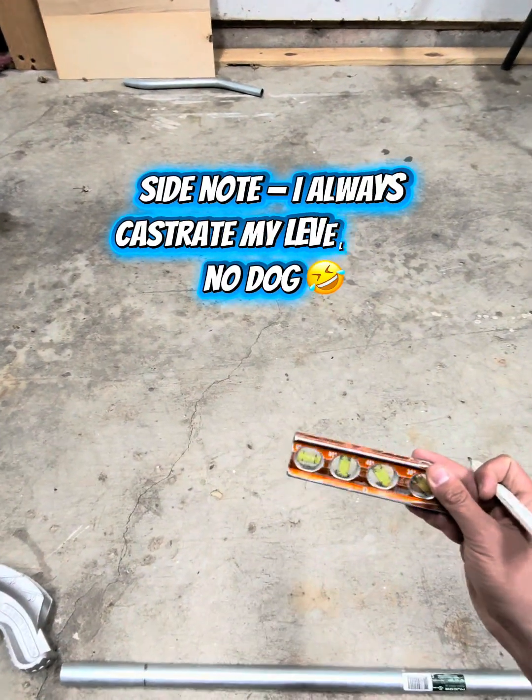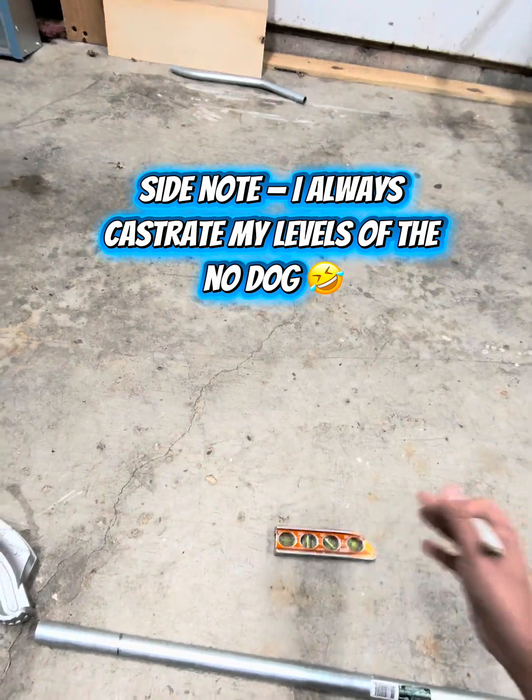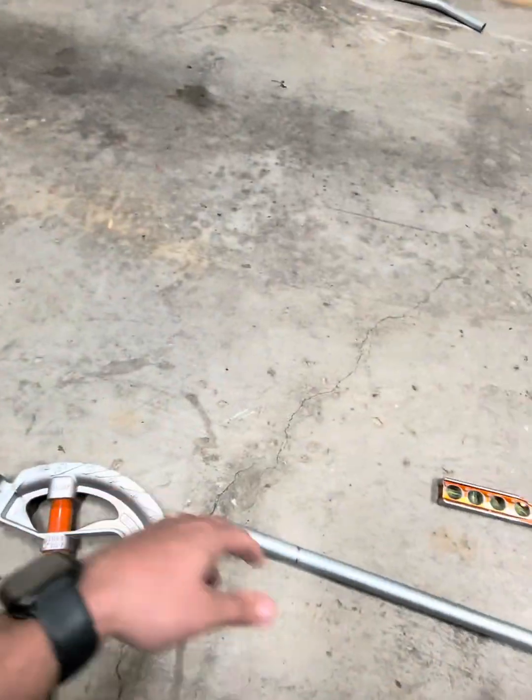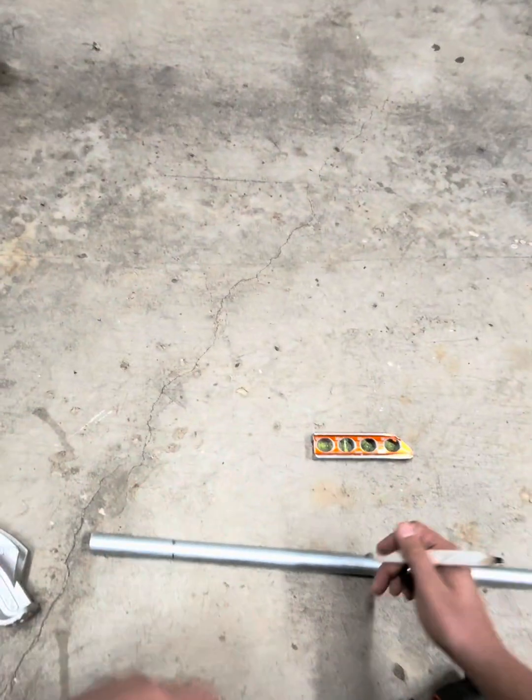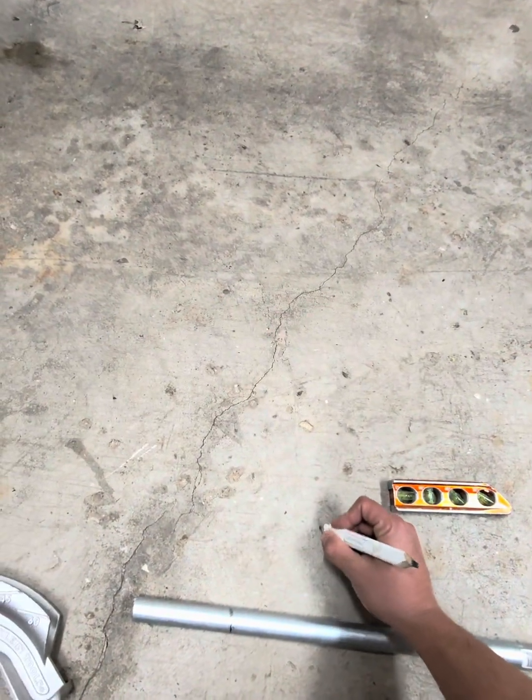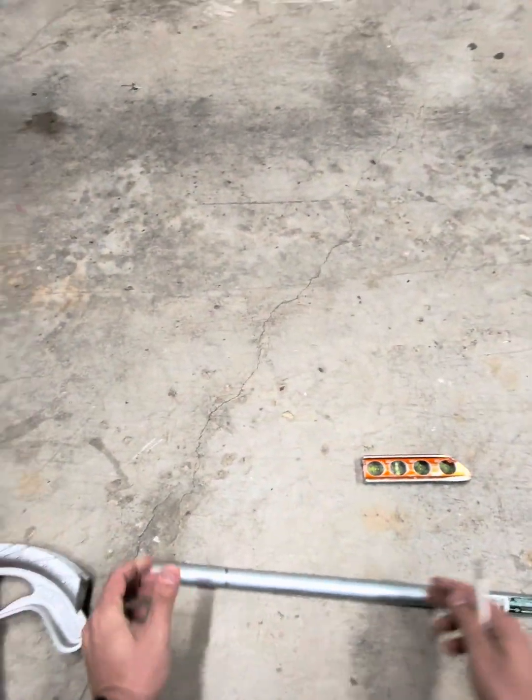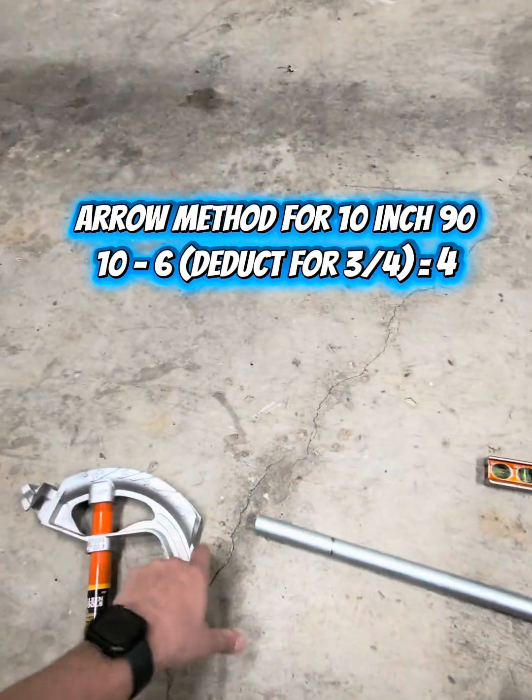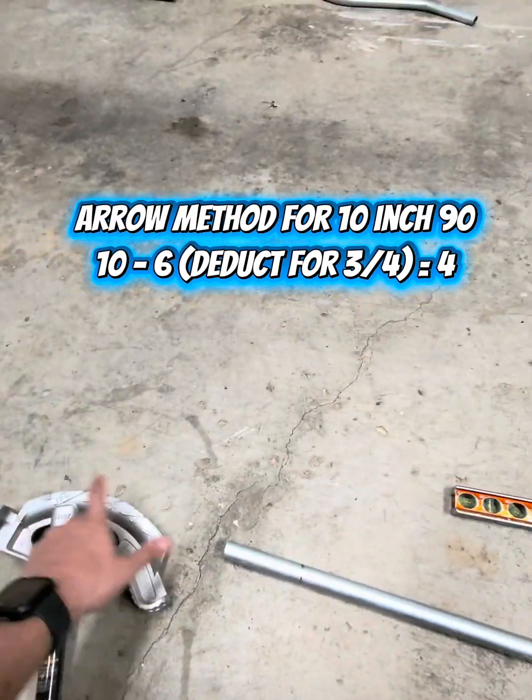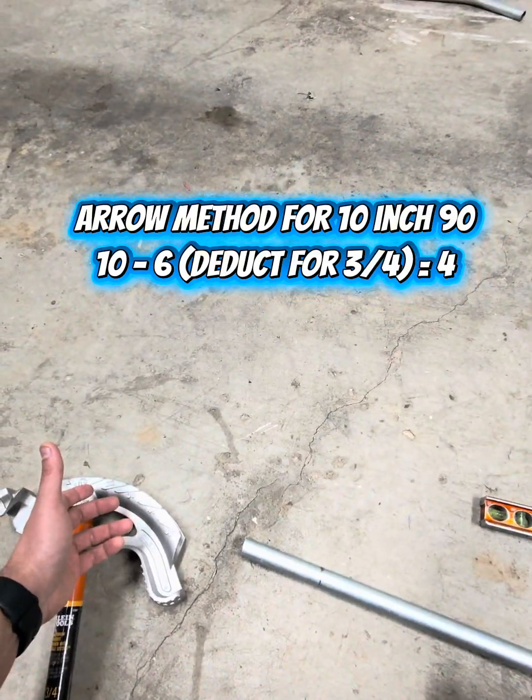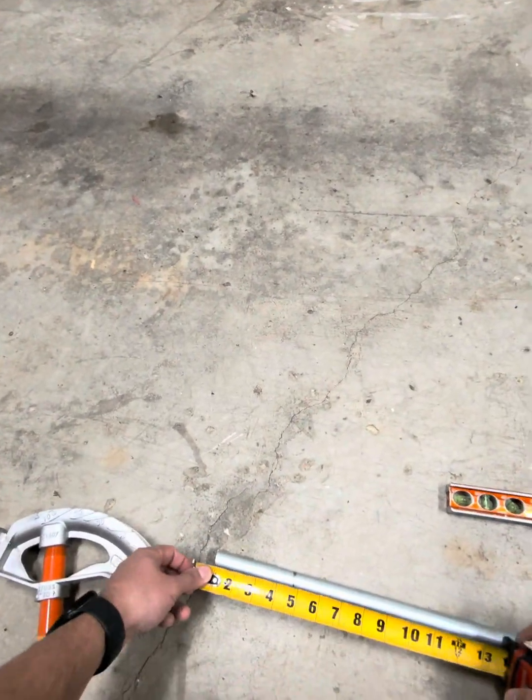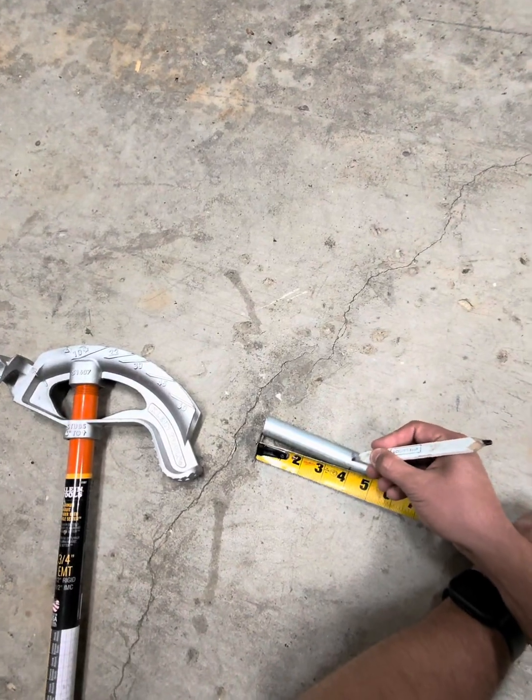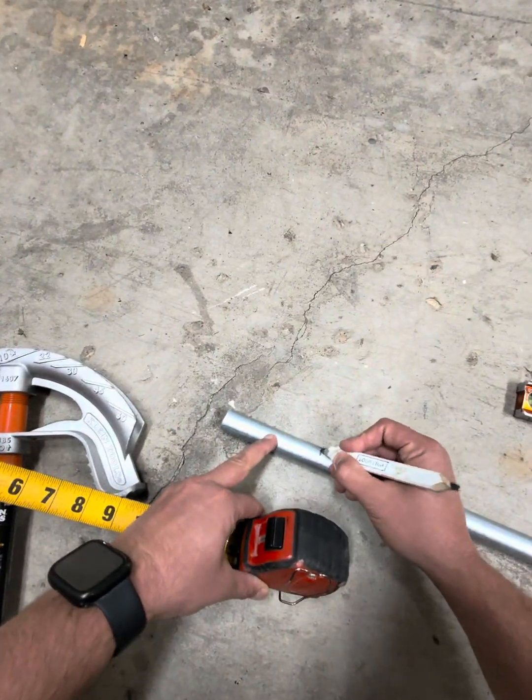Also, shout out to my castrated Klein level. I cut the nub off all mine. Anyways, the standard arrow method is going to be just as it sounds. So let's write it out on my concrete. Let's say I need a 10 inch 90. Our standard deduct on three-quarter EMT conduit in the hand bender is going to be six inches. So if I need a 10 inch 90, the standard deduct six inches, our mark would be at four inches, which I already have marked out.